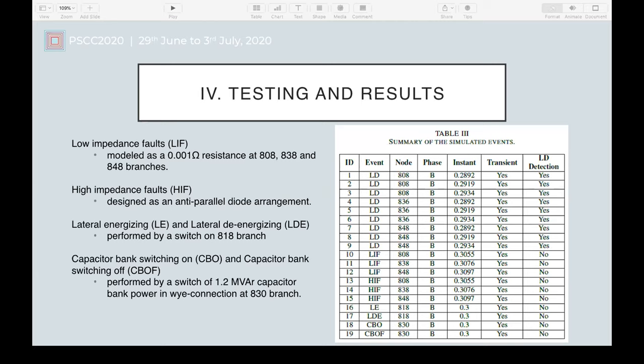The signal is scanned from start to end of the data and the energy maximum values associated with the detail coefficients of the direct and zero components are identified. The last part is fault classification. It makes the difference between the maximum points observed after the transient occurrence of the direct and zero components of energy. Whether this difference is over 100,000 means a direct lightning discharge has reached the distribution system.